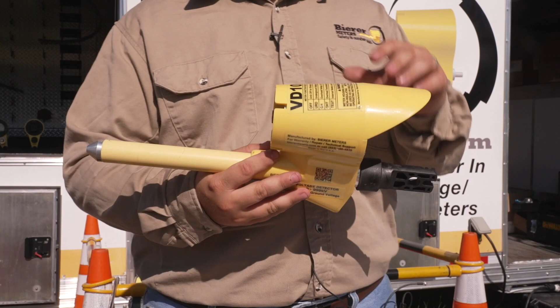The reason for that again is because everybody's tools, we've already talked about, have conductive components inside that make the tool work. So if you were to get this meter head nearby a potential ground or a hot phase while you're making contact down here at the probe, these conductive components could essentially cause a path across those two components. It would be an external flash. It's not going to hurt the tool at all, but it creates an unsafe working habit, and we don't want to do that. With that line limiting mark, you're going to want to think of it as a radius around the outside of the tool of where you want to keep any type of hot phase or a ground potential away from these devices.